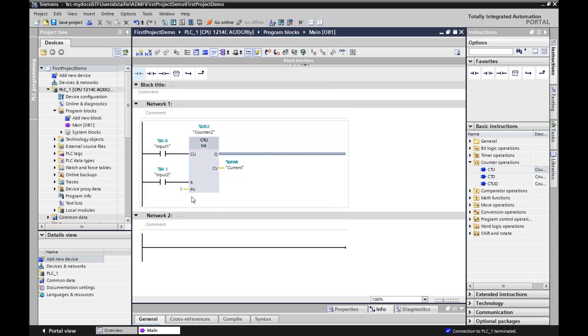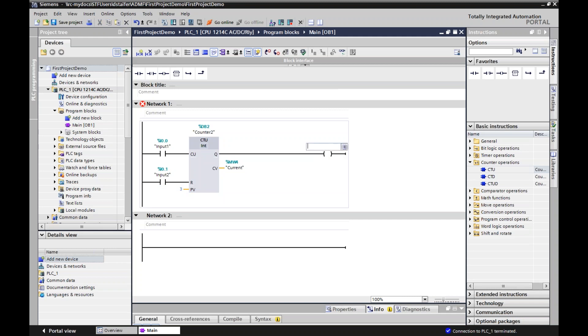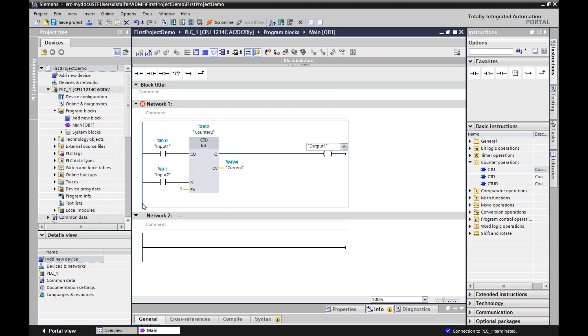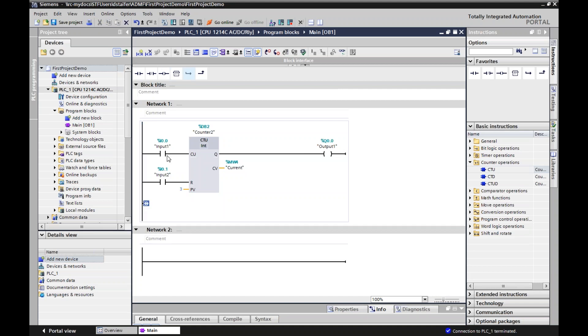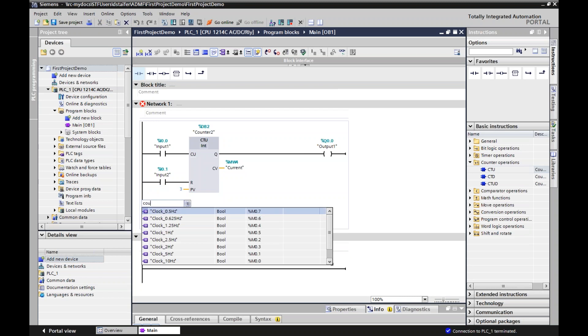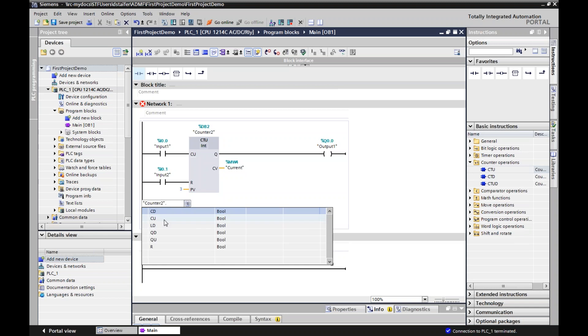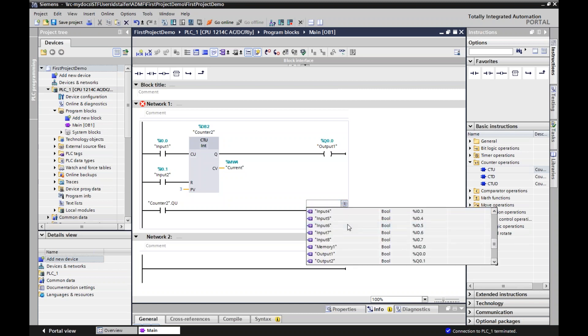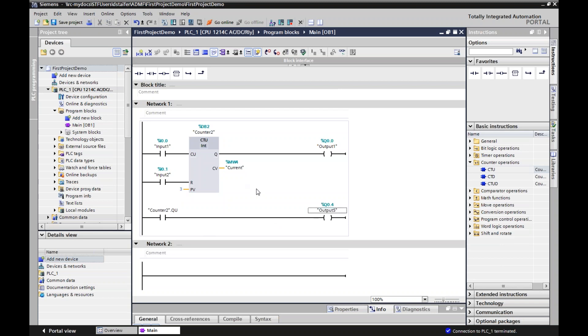Here is a reset. I can put in a bit command here and I can say make this input number 2. And then here I can put in input number 0 or input number 1. And what happens is when this goes true, it will count up 1. And then once the count hits 3, it will then turn on your Q bit here. You can either put in an output energize over here, output 1, or you can put in counter two dot Q. And here's my Q, in this case the Q up because this is the counter up. And turn on another light. So I'll put in an output 5.